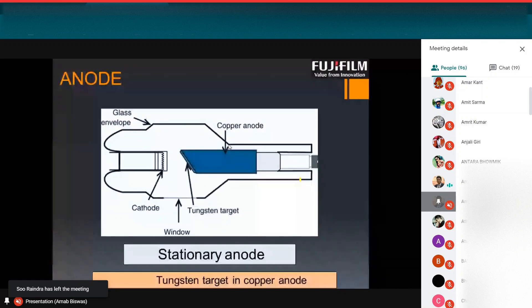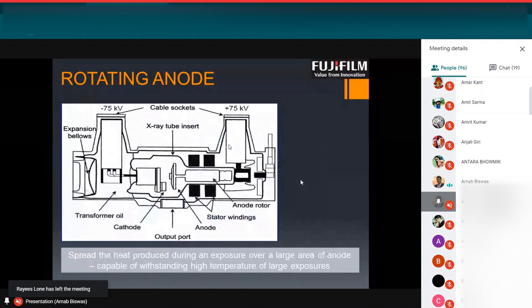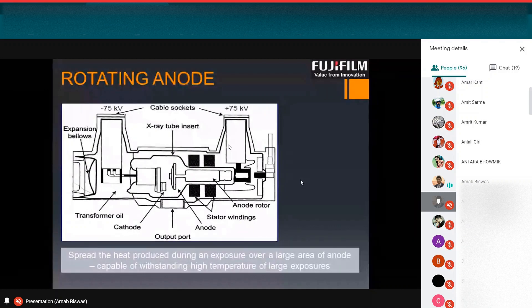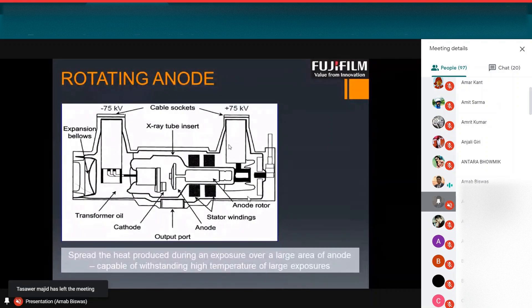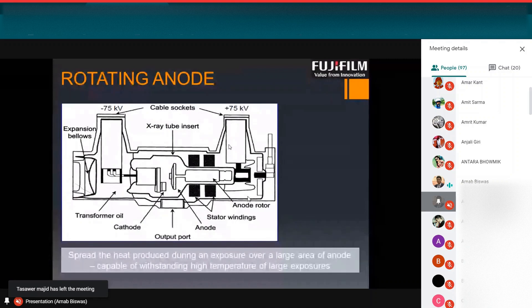This is rotating anode. As I previously discussed, what happens in a tube, in an X-ray tube, a tungsten filament is heated by electric current and it releases negatively charged electrons by thermionic effect. Due to high voltage potential difference between cathode and anode, the electrons are thus accelerated and hit the anode target.